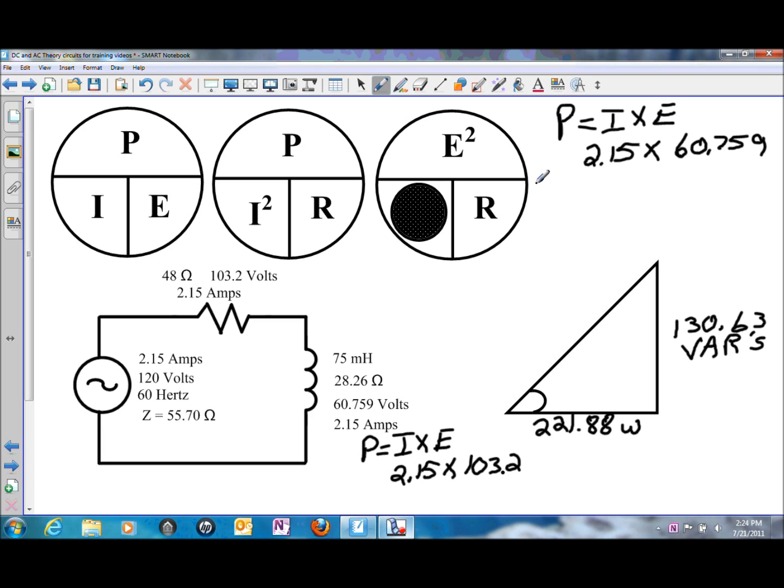Or we could apply Pythagoras theorem, which would be the watts squared plus the VAR squared to give us the total. And it provides you a means to prove it also. So I times E, or 2.15 amps of current flow, and this is going to be for total power, times 120 volts will give us 258 volt amps.